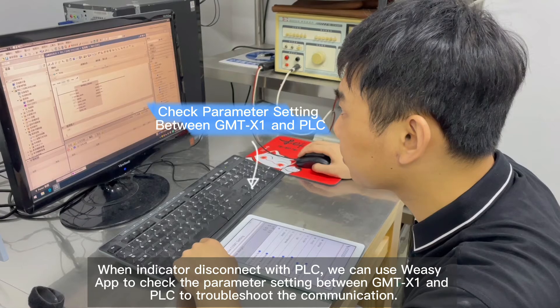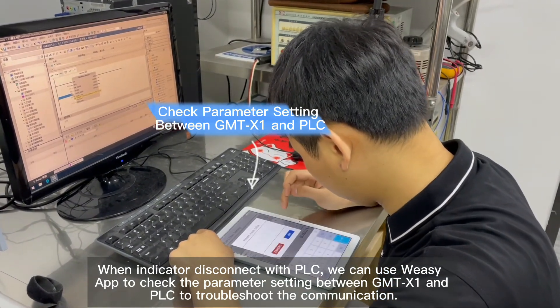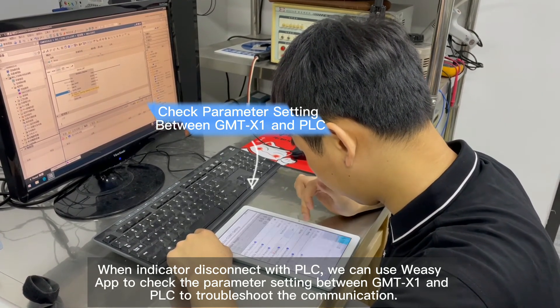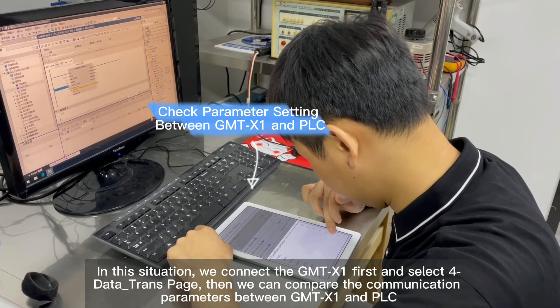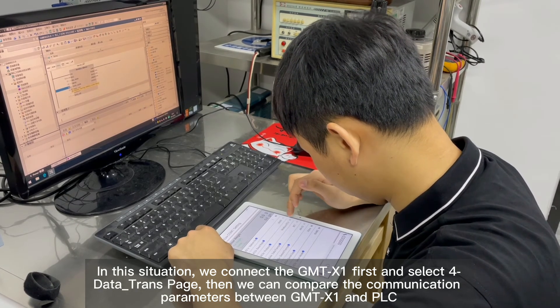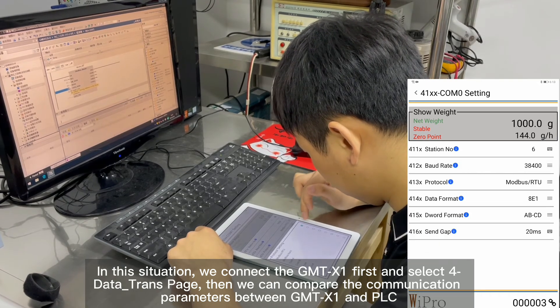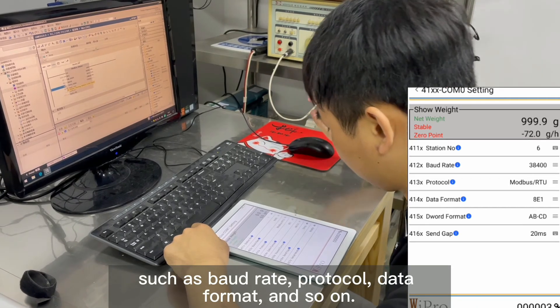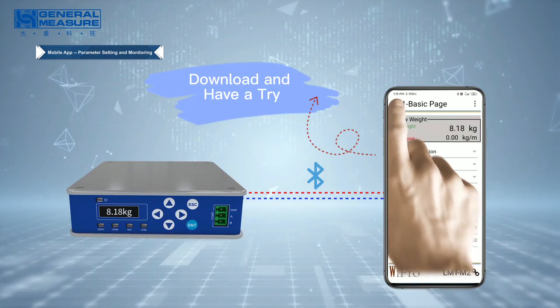When the indicator disconnects from the PLC, we can use Weasy App to check the parameter settings between GMT-X1 and PLC to troubleshoot the communication. In this situation, we connect the GMT-X1 first and choose the 4-Data_Trans page. Then we can compare the communication parameters between GMT-X1 and PLC, such as Baud rate, protocol, data format, and so on.